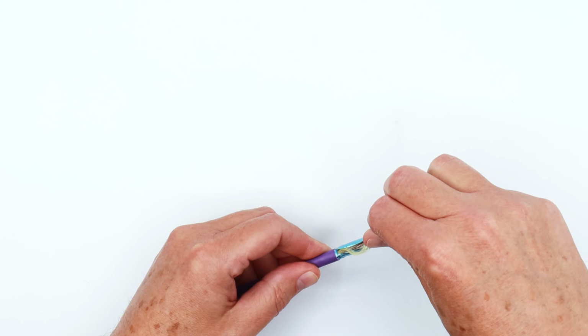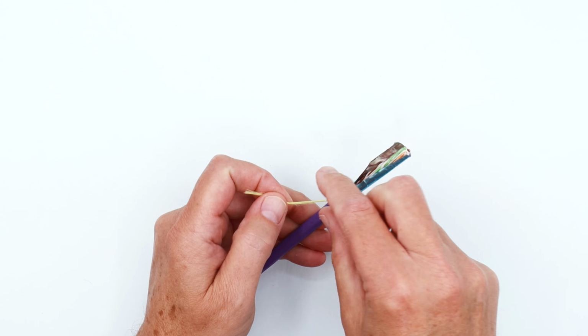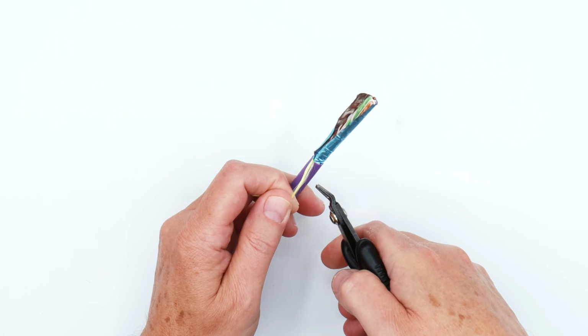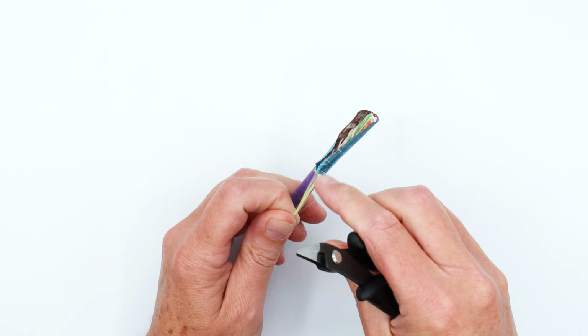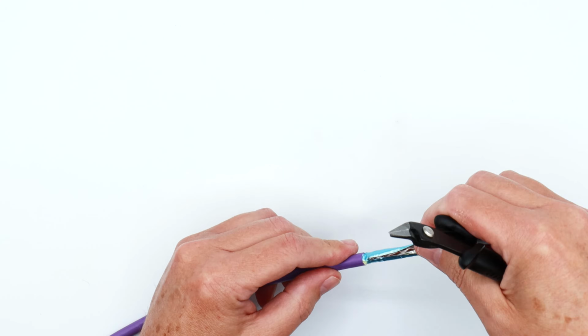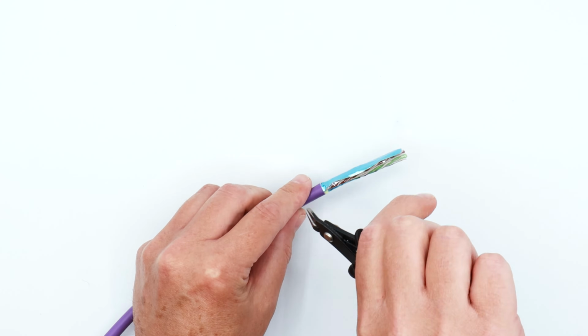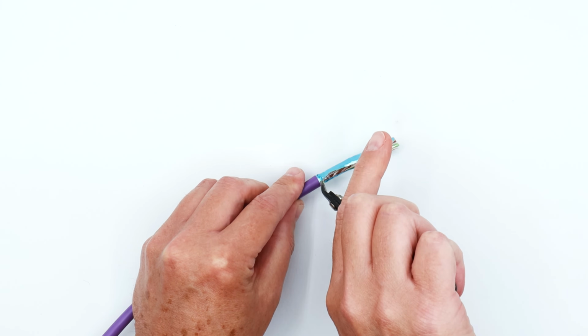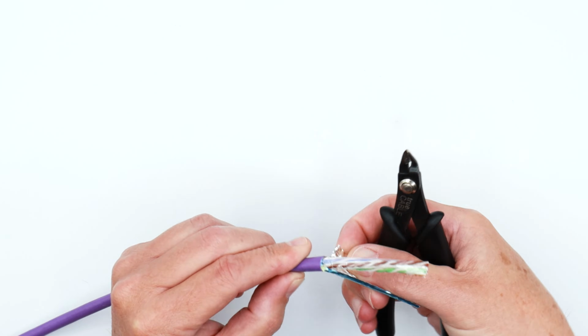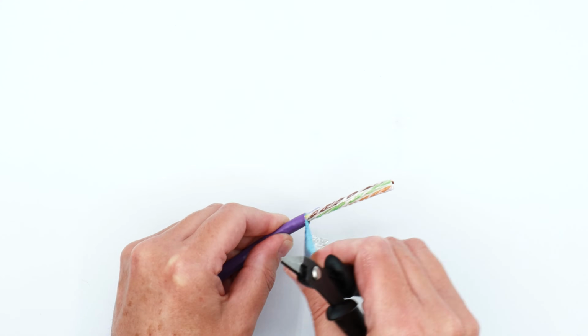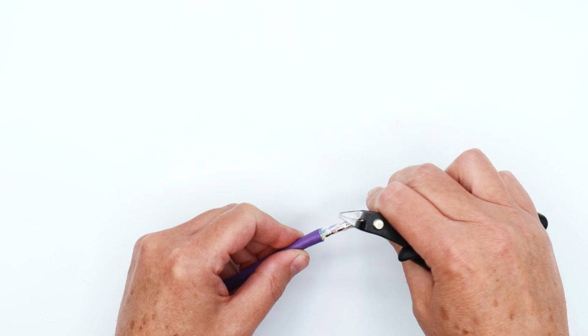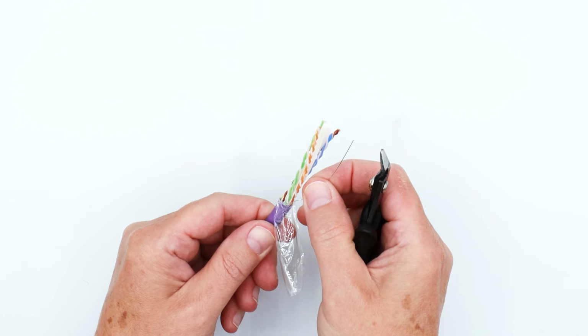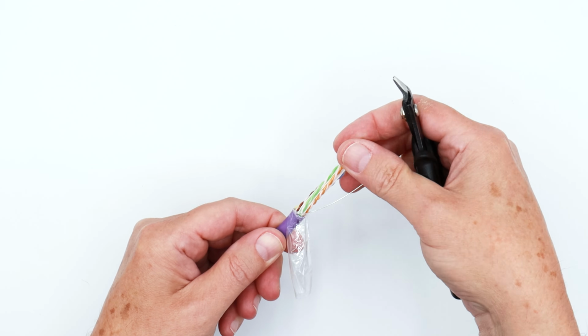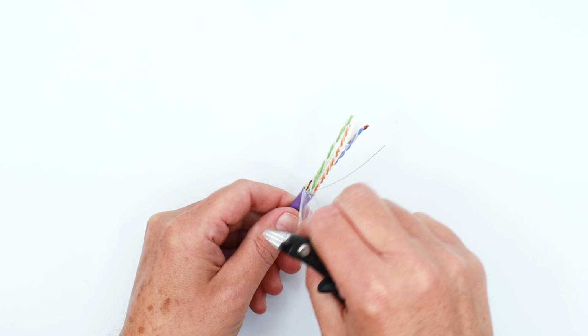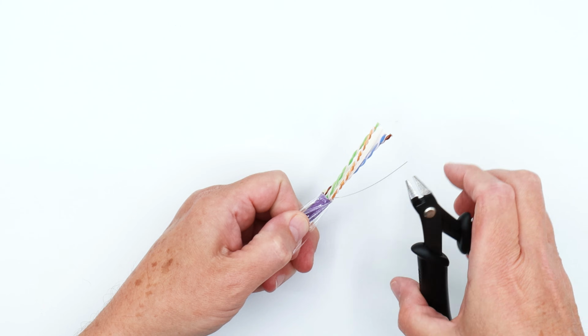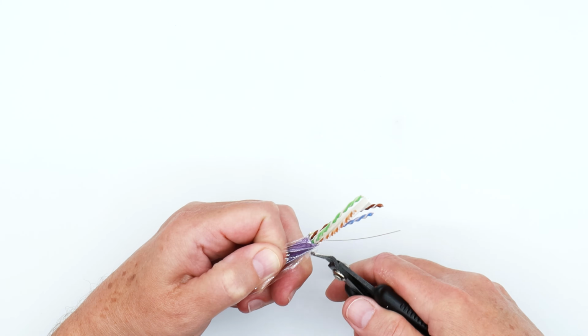So we're going to go ahead and get this propped up. This is the rip cord in the cable. I'm going to go ahead and remove the rip cord. And then we're going to remove the cable shield. And you're going to make a small nip at the very jacket edge, just like so, and remove the cable shield and discard it. Now what you'll find is a drain wire, a spline, some conductor pairs, and this polyester wrap tape. You want to remove the polyester wrap tape as well.